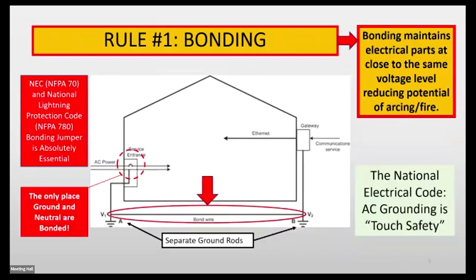Next thing: bonding. Here we go again. If you look at this, referencing back to the National Electric Code, it says if you have separate ground rods anywhere at your house, they need to be bonded together—I don't care if they're outside the house, ground rods are always outside, right? They need to be connected together with a large enough conductor to carry the current between them and keep them at equal potential.